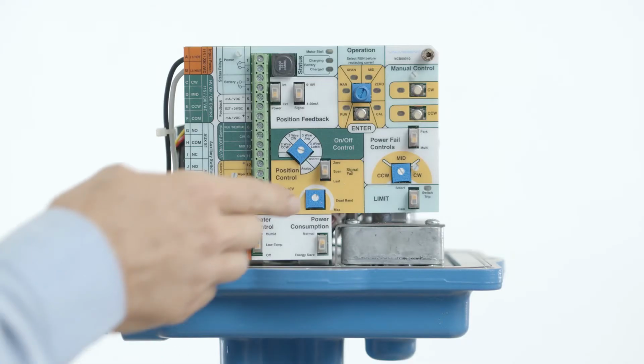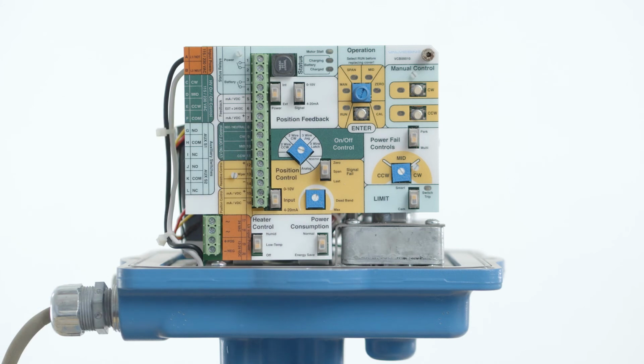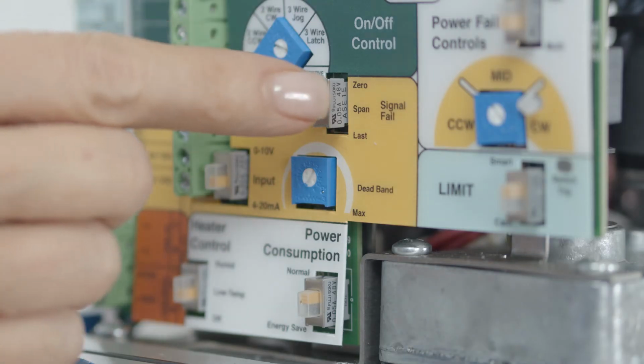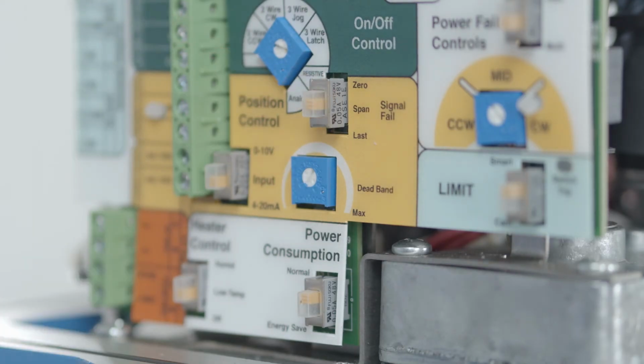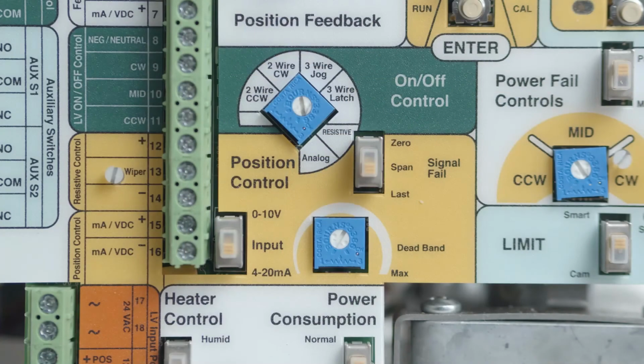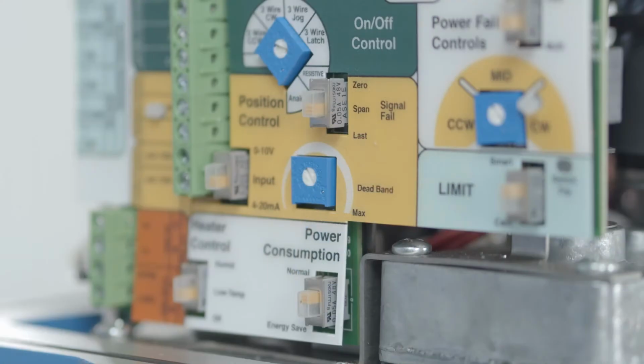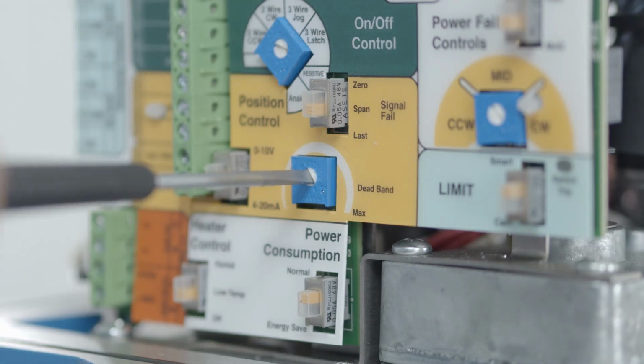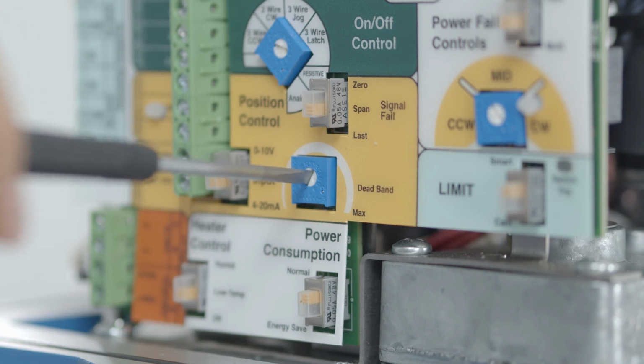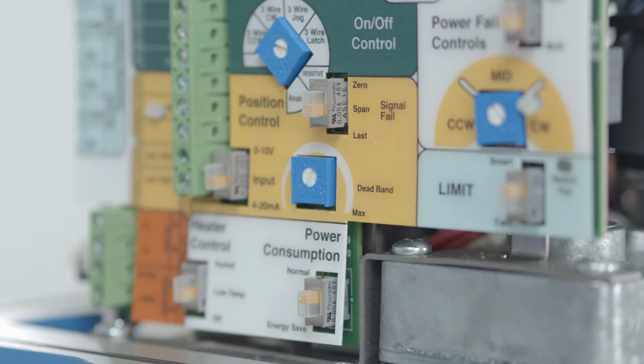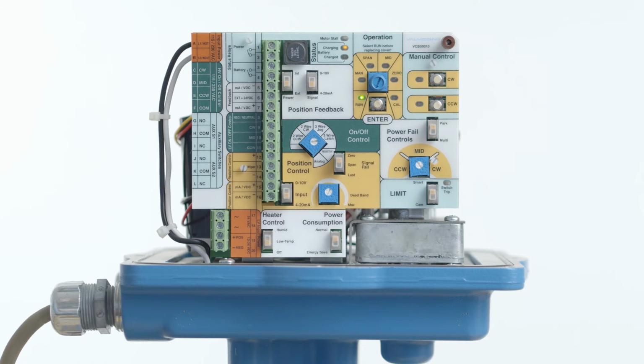To set this position, slide the selector switch all the way up to select 0, to the middle position to select span, or all the way down to select last. There is also a deadband adjustment that will increase or decrease the actuator's sensitivity to a signal change. This can be used to eliminate hunting if there is noise on the control signal. The minimum deadband will provide the most sensitive response. We recommend using the lowest setting at which no hunting occurs.